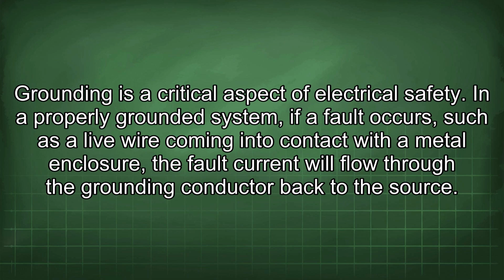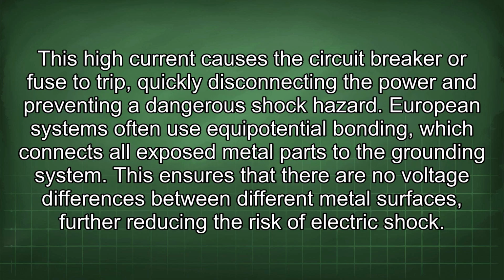Grounding is a critical aspect of electrical safety. In a properly grounded system, if a fault occurs, such as a live wire coming into contact with a metal enclosure, the fault current will flow through the grounding conductor back to the source. This high current causes the circuit breaker or fuse to trip, quickly disconnecting the power and preventing a dangerous shock hazard. European systems often use equipotential bonding, which connects all exposed metal parts to the grounding system. This ensures that there are no voltage differences between different metal surfaces, further reducing the risk of electric shock.